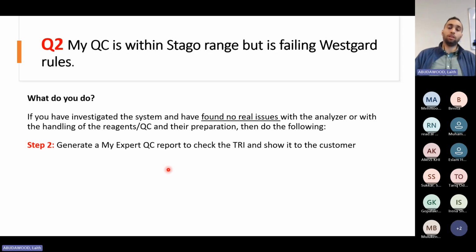Now, if I have applied my Westgard rules and I suspect that I have a problem with the precision, or I suspect that I have a problem with bias, please keep in mind that Westgard rules are not diagnostic of problems. They are meant to alarm you that there are possible problems, okay? A Westgard rule tells you that maybe you have a bias, investigate, check. It doesn't tell you you certainly have bias. You need to investigate that and confirm it through other means.